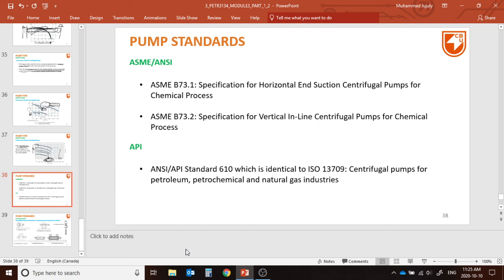Codes we have for the pumps. The codes and standards, like the ASME or ANSI code B73.1, give the horizontal end suction centrifugal pump for the chemical process, and B73.2 is for vertical inline centrifugal pumps for the chemical process.